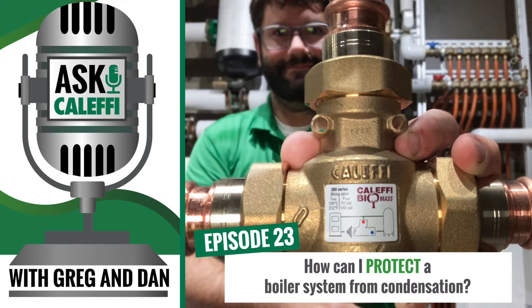It makes a mess. You need to look at your lower temperature applications — that's where modulating boilers are a great fit. But initially trying to heat a system or building up, you don't want to risk condensing that cast iron boiler. You're going to throw a shock at that boiler, 100% every day of the week.